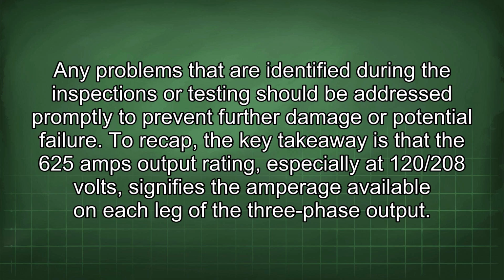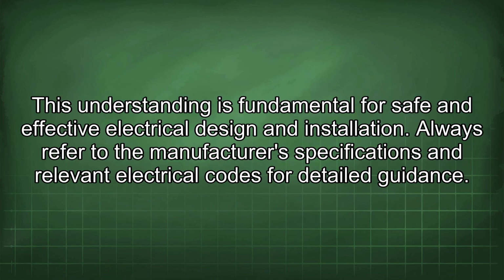To recap, the key takeaway is that the 625 amps output rating, especially at 120/208 volts, signifies the amperage available on each leg of the three-phase output. This understanding is fundamental for safe and effective electrical design and installation. Always refer to the manufacturer's specifications and relevant electrical codes for detailed guidance.